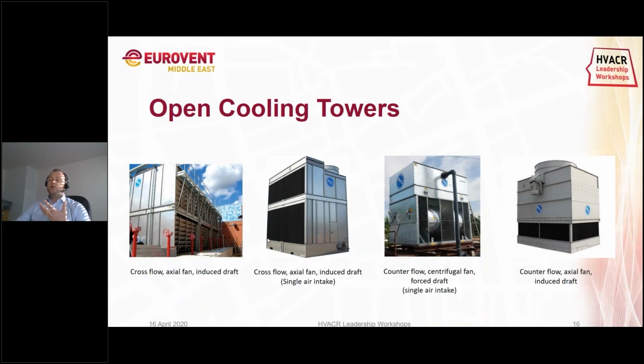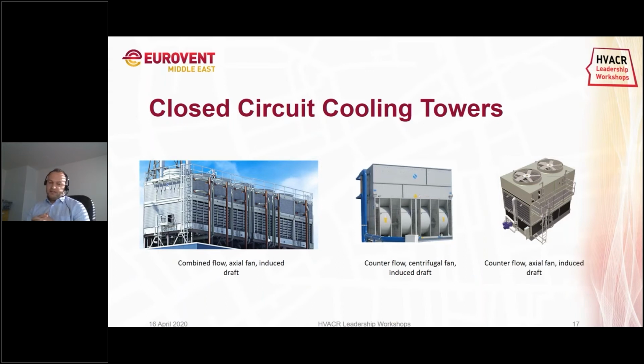Next to the solution with the open cooling towers, we also see a possibility for the closed cooling towers. The big difference is that closed cooling towers prevent airborne contaminants from entering the system. So there is less possibility of fouling. In these kinds of products, there is minimal water treatment and also minimal maintenance required. And we have here a closed loop in a single piece of equipment. Same as for the open towers, we have cross-flows, we have counterflows, with centrifugal fans and with axial fans, depending on the restrictions in a specific project.